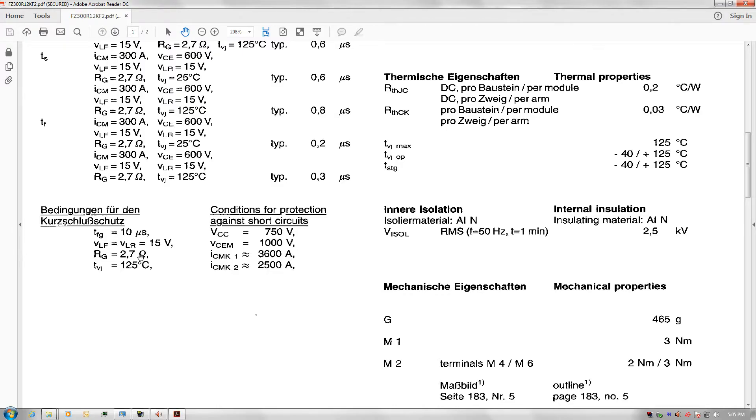The value of acceptable gate resistors is usually this value multiplied by 10. So for this IGBT, it's about 2.7 ohms up to 27 ohms.